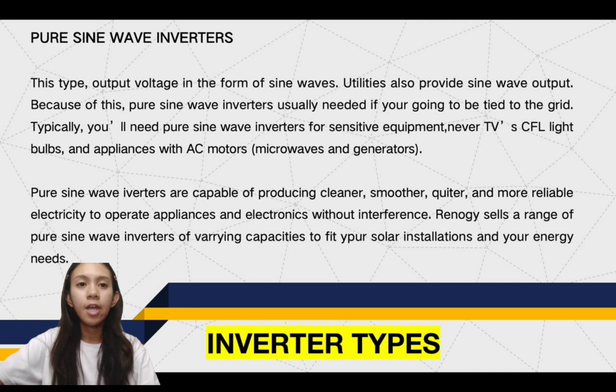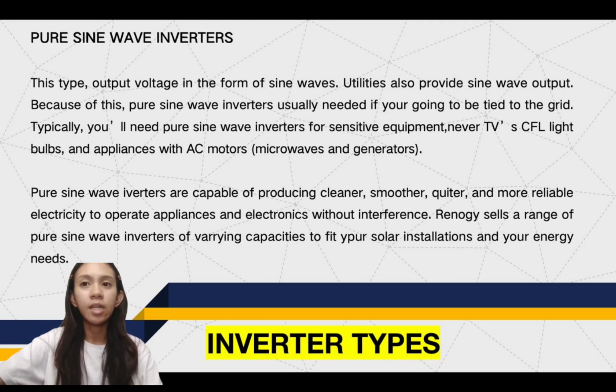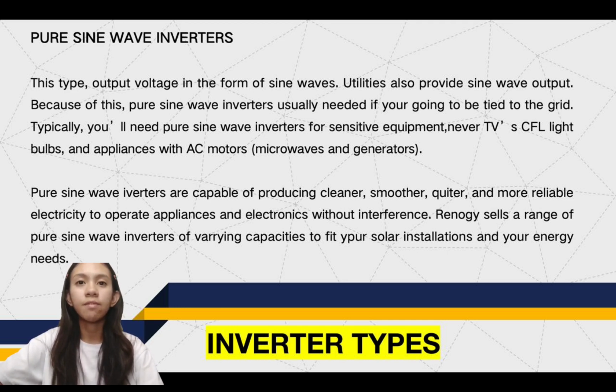As for pure sine wave inverters, this type outputs voltage in the form of sine waves. Utilities also provide sine wave output. Because of this, pure sine wave inverters are usually needed if you're going to be tied to the grid. Typically, you need pure sine wave inverters for sensitive equipment, newer TVs, CFL light bulbs, and appliances with AC motors, microwaves, and generators. Pure sine wave inverters are capable of producing cleaner, smoother, quieter, and more reliable electricity to operate appliances and electronics without interference.